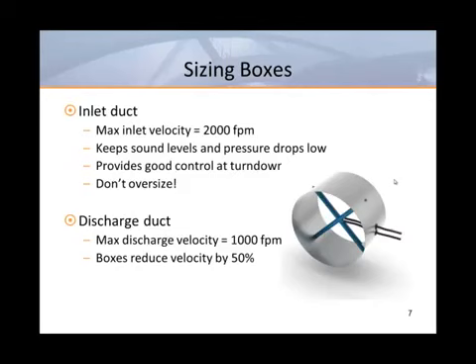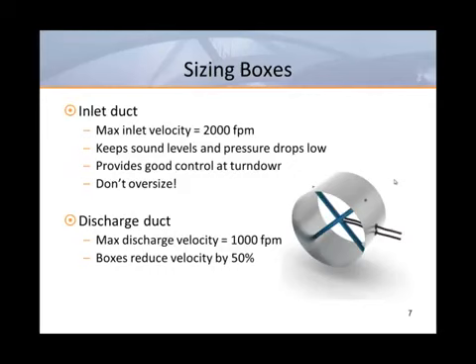Besides control problems, oversized inlets can also cause noise problems. Selection software can predict noise levels at maximum flow based on inlet velocity and pressure, but oversized inlets can result in air squeaking around damper seals at minimum flow, resulting in pure tone noise. Since the noise created is dependent on pressure, the condition of the damper seals, and the roundness of the duct, this is a sound that cannot be predicted by any manufacturer's catalog or software.